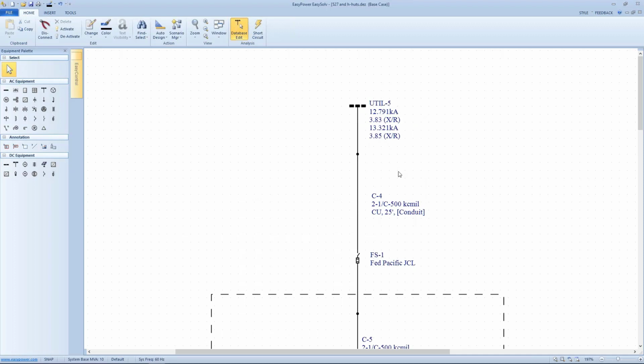And the other thing that's a little strange about the data, and I advise that you may want to double check, most of the time the single line to ground short circuit is less than the three-phase. Three-phase is usually higher, worst case current. So that's another word to the wise. So we're going to leave it as it is and assume that this is correct.